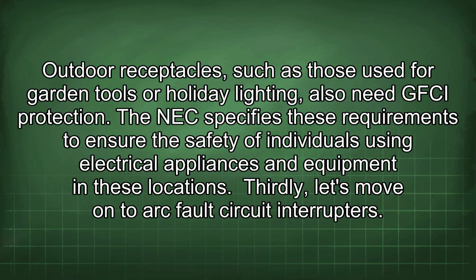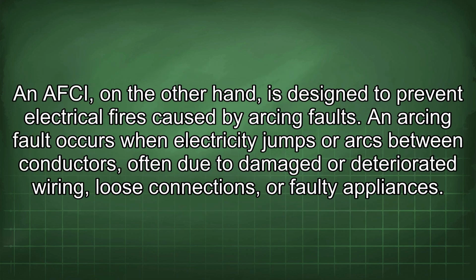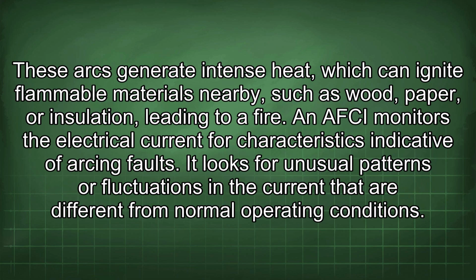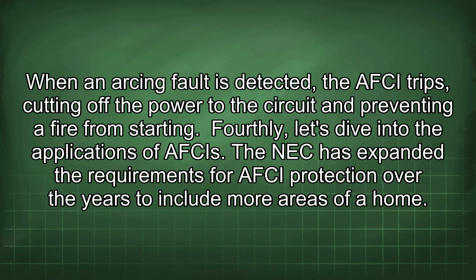Thirdly, let's move on to arc fault circuit interrupters. An AFCI, on the other hand, is designed to prevent electrical fires caused by arcing faults. An arcing fault occurs when electricity jumps or arcs between conductors, often due to damaged or deteriorated wiring, loose connections, or faulty appliances. These arcs generate intense heat, which can ignite flammable materials nearby, such as wood, paper, or insulation, leading to a fire. An AFCI monitors the electrical current for characteristics indicative of arcing faults. It looks for unusual patterns or fluctuations in the current that are different from normal operating conditions. When an arcing fault is detected, the AFCI trips, cutting off the power to the circuit and preventing a fire from starting.